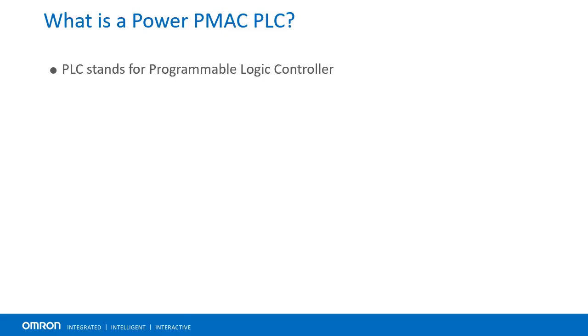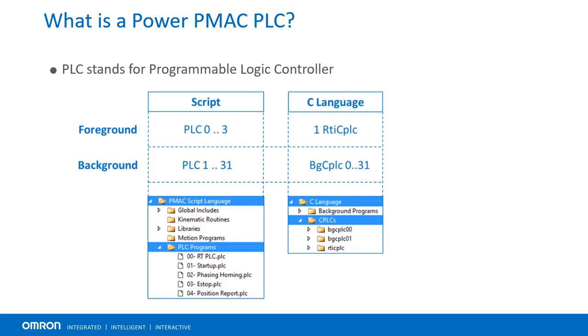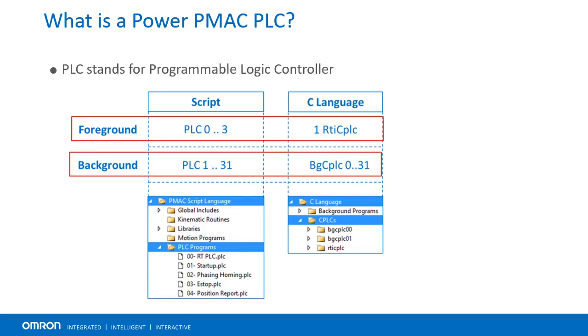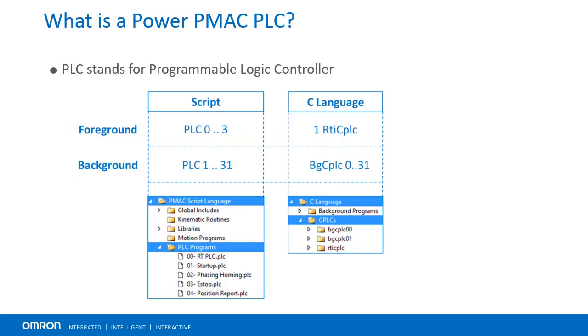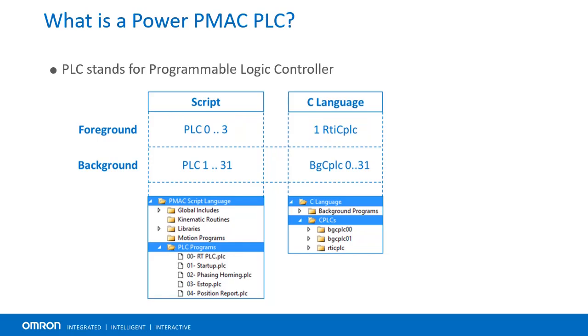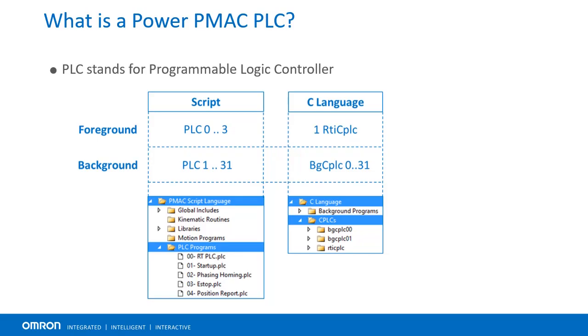In PowerPMAC there are two types of PLC programs, foreground and background. Foreground PLCs scan deterministically at a preset high priority frequency such as servo update. Background PLCs on the other hand, as suggested by their name, scan freely after higher priority tasks in the leftover CPU processing time.